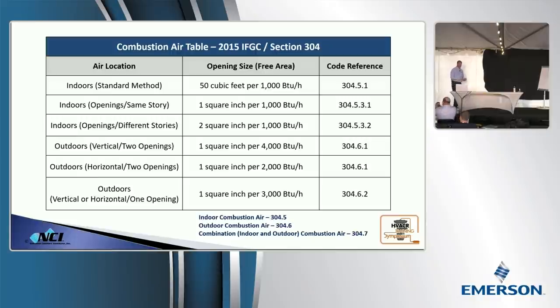As you look at this table, which I just made up in Word, for indoors you have to look at the conditioned space. You have to see the amount of cubic feet, or volume, that you have per 1,000 BTUs of the equipment. Of course, you've got the corresponding code references up there. We also have to consider where we are taking the air from. If it's from indoors, how many openings are typically used for combustion air? One or two? Typically it's two. You can get away with one. Canadians like one for some reason. But we're making some assumptions with that. You can see we've got all kinds of different numbers up here: 1 square inch per 1,000 BTUs, all the way up to 1 square inch per 4,000 BTUs, depending on the location. Now, how do we know this works?